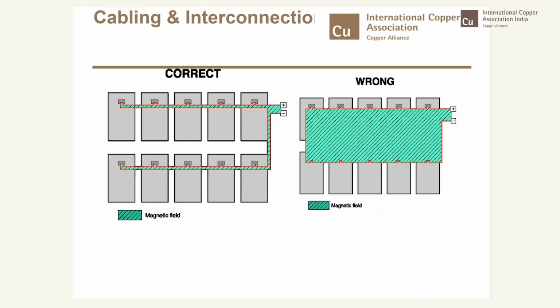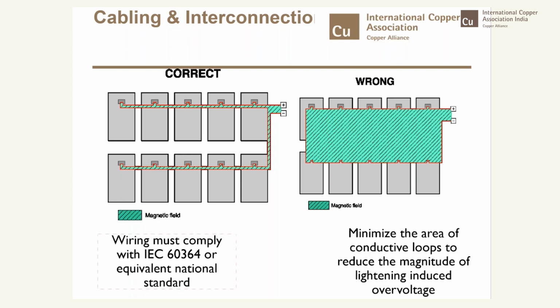All the associated equipment and components in the balance of system also need to survive for their maximum life period. A very useful tip when you do the array wiring: you can see the correct and wrong methods of wiring. The idea is the area of conductive loops has to be reduced. The positive cable is taken, it is looped serially, and then finally when it is connected to the array junction box, the magnetic loop area formed is quite large in the wrong practice. You look at the left side, which is the correct practice. Even though you may have to use a little extra cable, here the loop area is very small. So this reduces the risk of lightning induced voltages in the cable. It is a practice which many of us unfortunately do not follow.